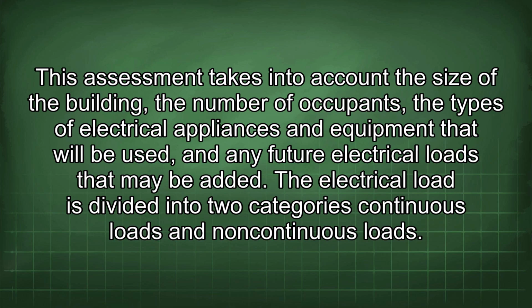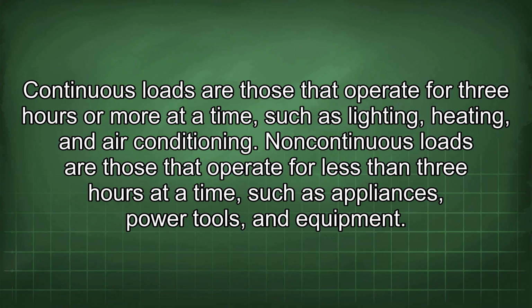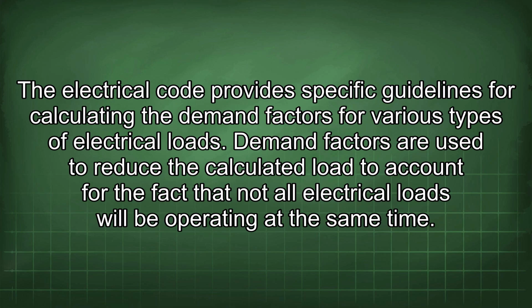The electrical load is divided into two categories: continuous loads and non-continuous loads. Continuous loads are those that operate for 3 hours or more at a time, such as lighting, heating, and air conditioning. Non-continuous loads are those that operate for less than 3 hours at a time, such as appliances, power tools, and equipment. The electrical code provides specific guidelines for calculating the demand factors for various types of electrical loads. Demand factors are used to reduce the calculated load to account for the fact that not all electrical loads will be operating at the same time.